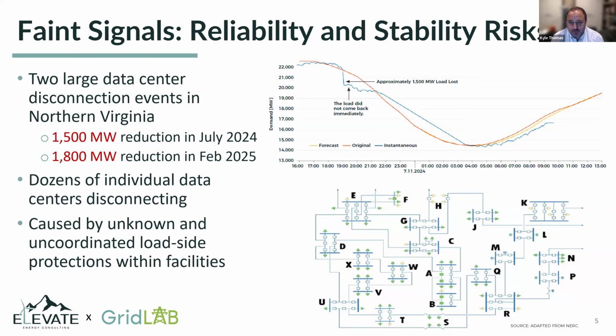There's been a lot of presentations and papers on these topics, but there were two large data center trip events, or disconnection events, that occurred in Northern Virginia. One was in July of last year, shown in the chart on the right, and another occurred in February. In July, that event was 1,500 megawatts of data centers tripping off or being reduced. In February, it increased to 1,800 megawatts. Not a good trend—that's a lot of megawatts tripped off from a grid event where, importantly, the utility wasn't expecting it to occur.